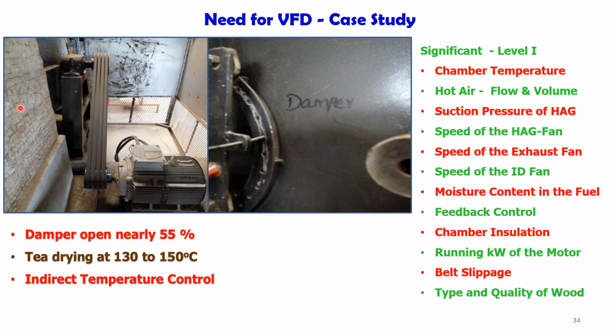Normally, the damper position will be adjusted based on the temperature required for the drying application. I told you the tea industries are mostly in hilly areas, so the temperature keeps varying throughout the day, and similarly with the season. So based on the ambient temperature and the tea drying process, they will change the damper to control the flow of the hot air. Mostly it is between 65 to 55%. Damper open 55% means it is closed 45%. That means the motor keeps running to produce enough air, but you are not allowing it; you are passing only 55% of the air to the system. The remaining you stop here. This is the case in most tea industries.